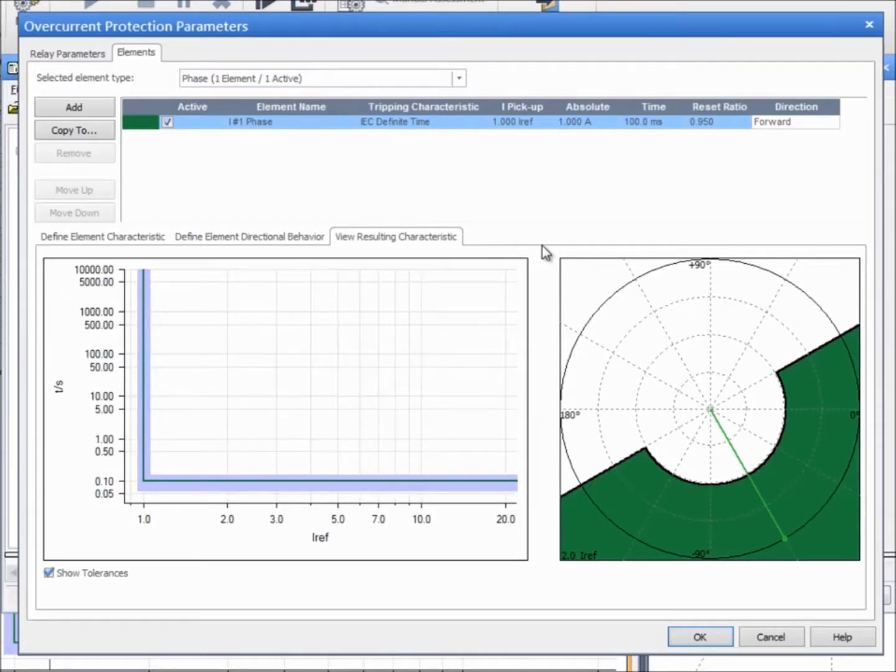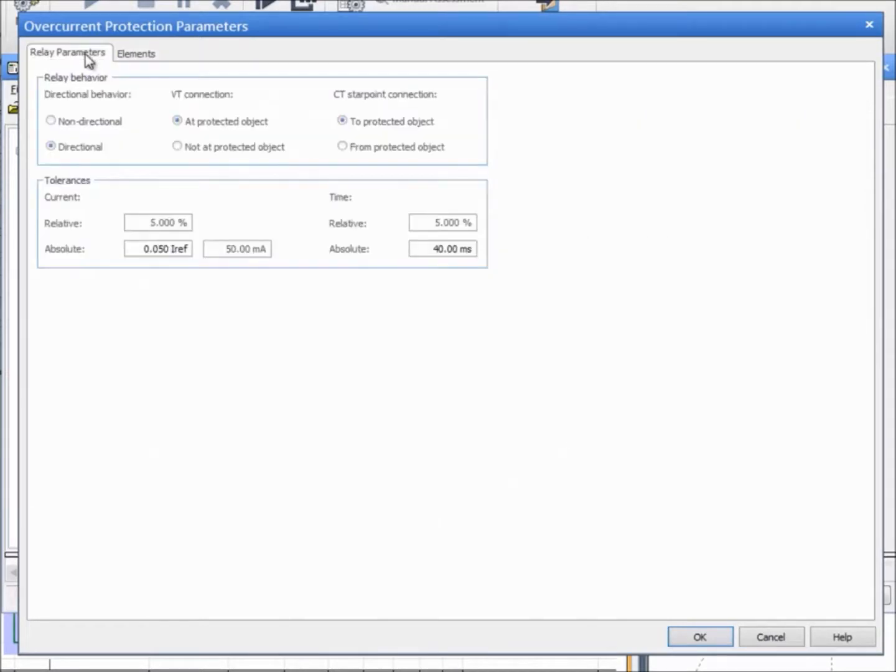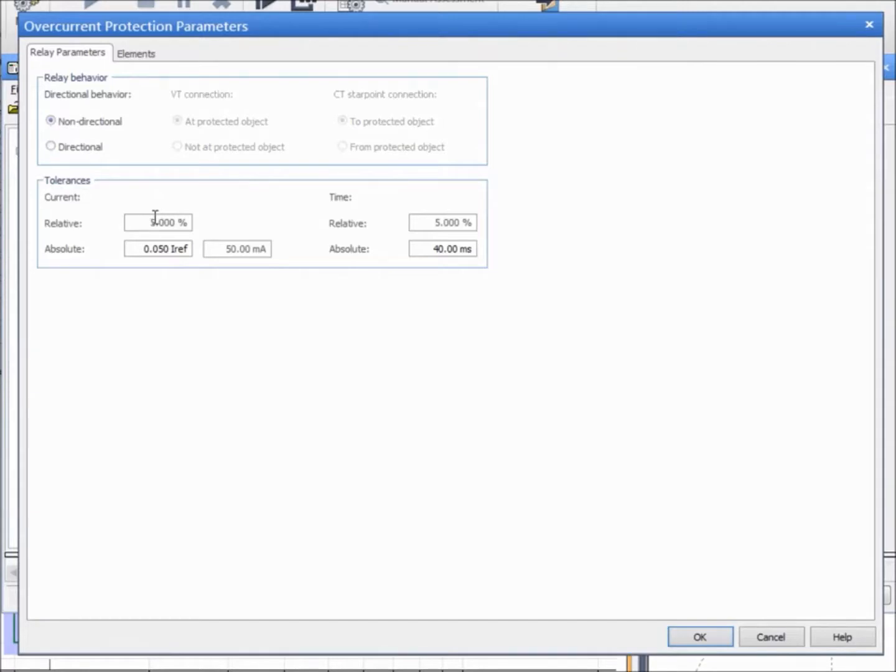To keep all these concepts in mind, we will proceed by configuring the overcurrent block according to the relay we are testing in the OCC file. That is, a non-directional relay with two definite time elements. First, we set the behavior to non-directional and we enter the corresponding tolerances of time and current.